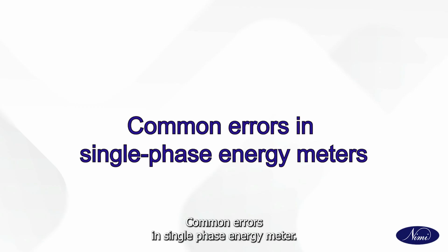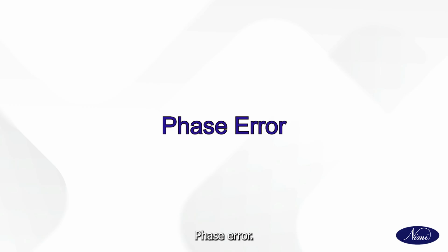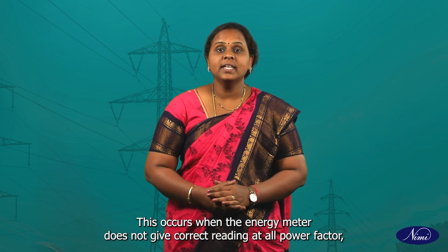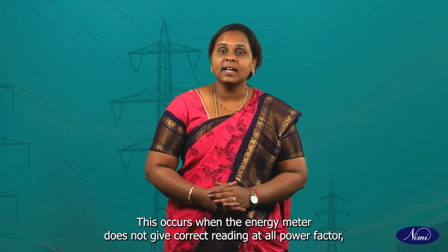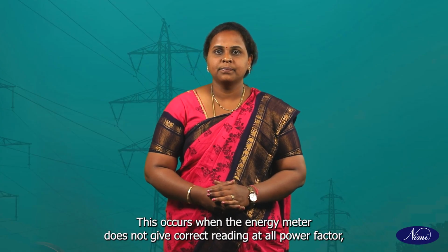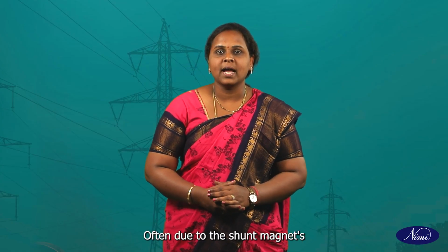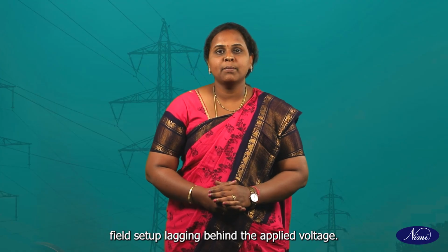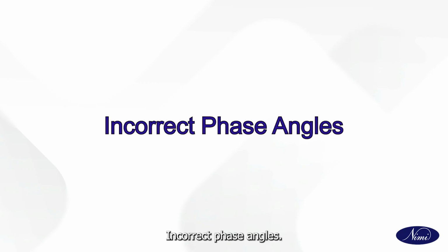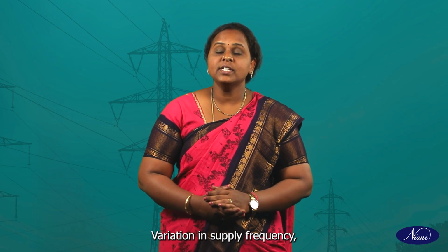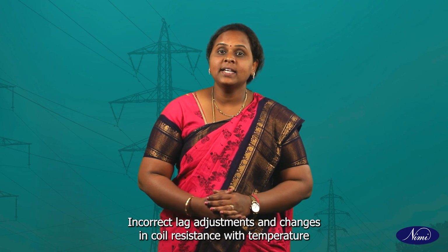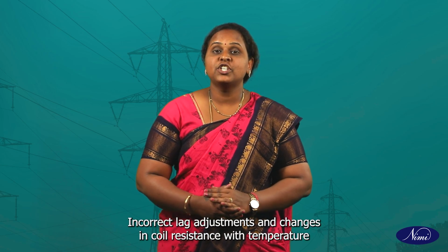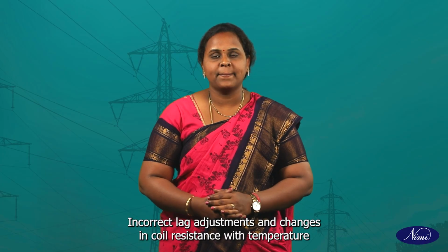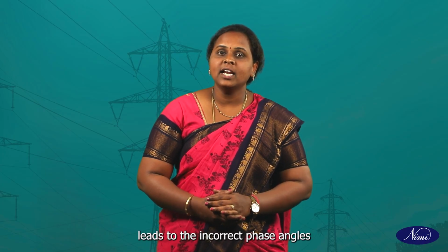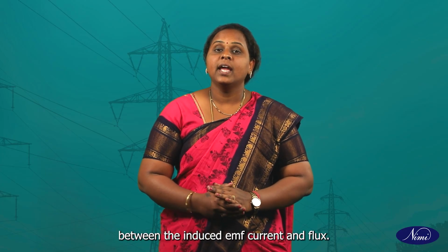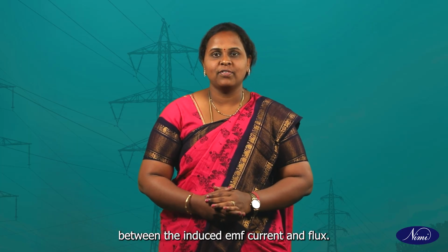The moving system attains steady speed when the driving torque equals the braking torque. Common errors in a single phase energy meter. Phase error. This occurs when the energy meter does not give the correct reading at all power factors, often due to the shunt magnet's field setup lagging behind the applied voltage. Incorrect phase angles. Variation in supply frequency, incorrect lag adjustments and changes in coil resistance with temperature lead to incorrect phase angles between the induced EMF, current and flux.